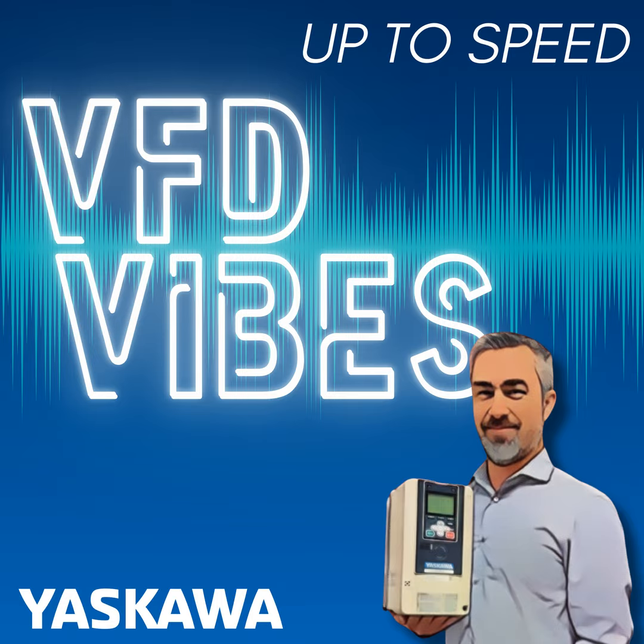And in fact, one of the things we've done in the application department is figured out exactly what a single phase rating for a typical drive would be. If the drive's designed for three phase, the typical single phase rating is somewhere between a third and a half of the three phase rating of the drive. And you have to look in the catalog to find out what that single phase rating would be.